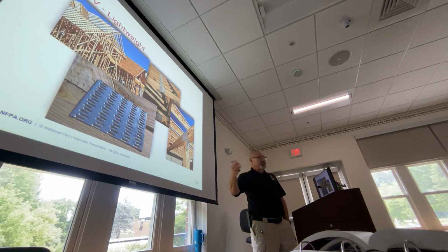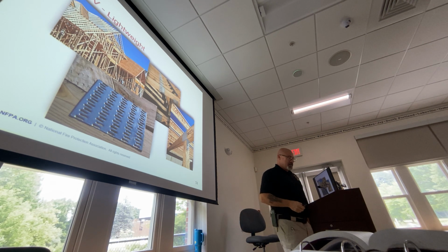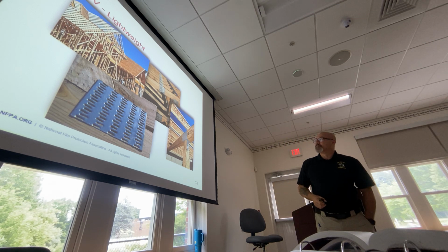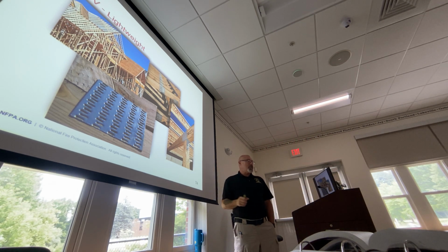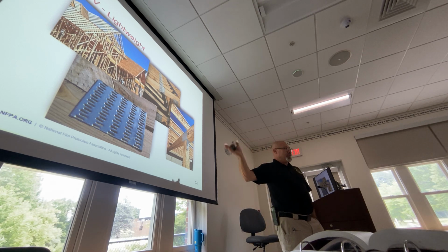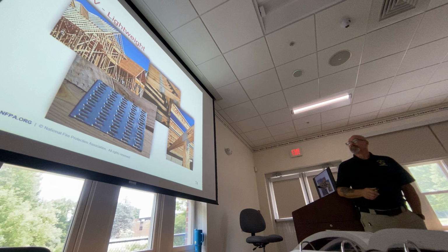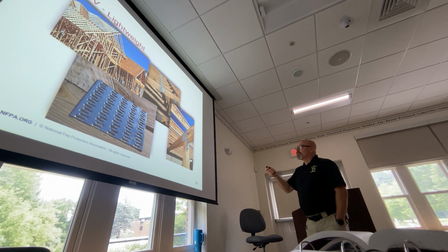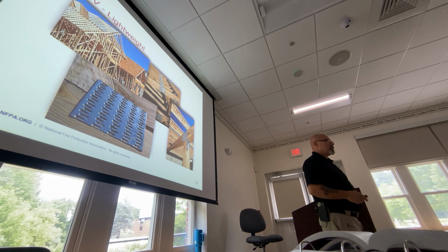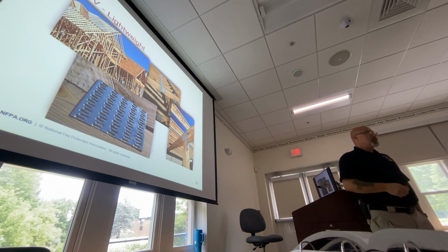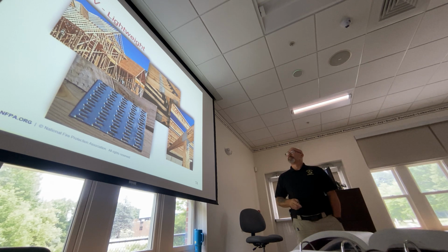So then, of course, that puts me in a spot. I'm working for my own client, knowing what the code requirements are, and the tough part was the person who designed the project was also the building official, so it created some sticky situations there. But if we see these, if they're exposed, they need to be protected. Plain and simple. Sheetrock them or put sprinklers in the building.